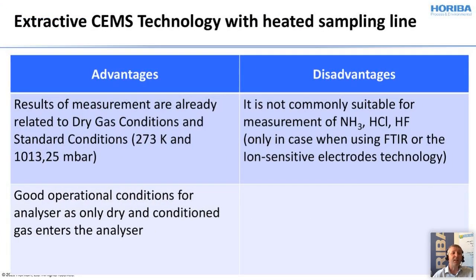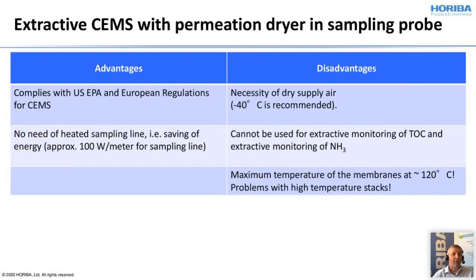The next advantage is that we have the results of measurement already based on dry gas conditions, and we don't need to correct them later on again. The disadvantage is also mentioned before, it is not commonly suitable for measurement of ammonia, hydrogen chloride, hydrogen fluoride without having FTIR or ion sensitive technologies. Coming to the advantages and disadvantages for the extractive CEMS with permeation dryer, it also complies with the US EPA and European regulations. And the further advantage I mentioned already, there is no need of the heated sample line, and you save a lot of electrical energy, about 100 watt per meter of the sampling line.